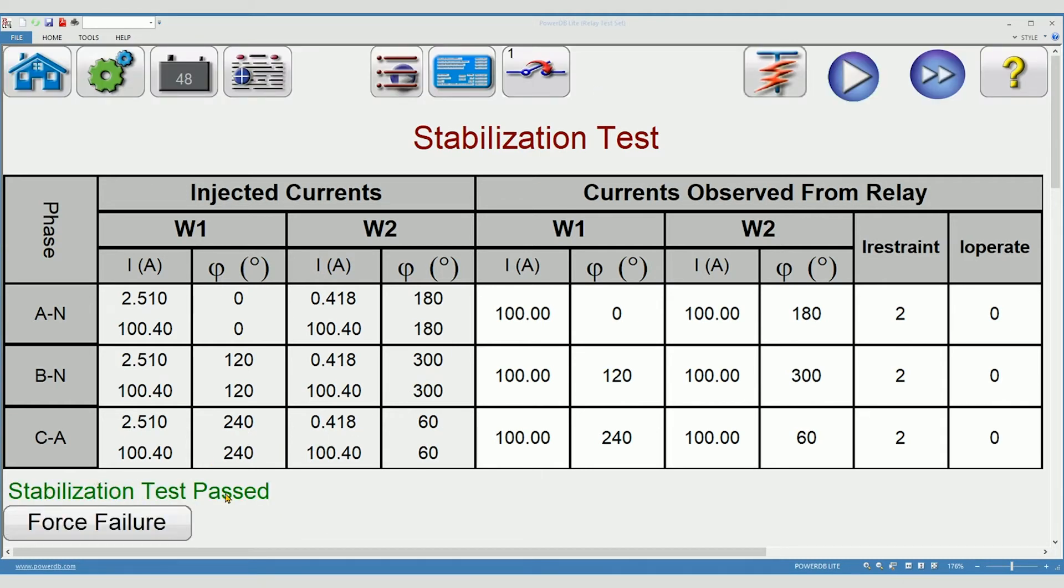Stabilization test passed. If you're reading high operate current, then you should press force failure and correct the problem. Now we'll proceed on to the next test, the timing test.